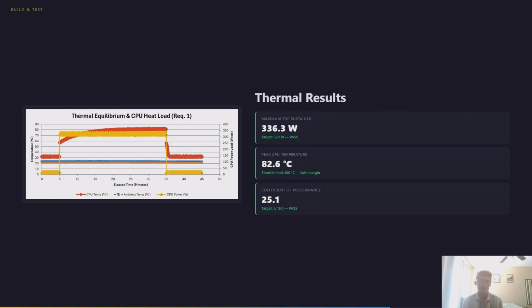The thermal results exceeded every target. The system maintained a continuous 336.3 watt heat load, well above our 320 watt goal. The CPU temperature plateaued at 82.6 degrees Celsius, which is 17 degrees below the throttling limit. This flat plateau confirms that true thermal equilibrium was achieved.